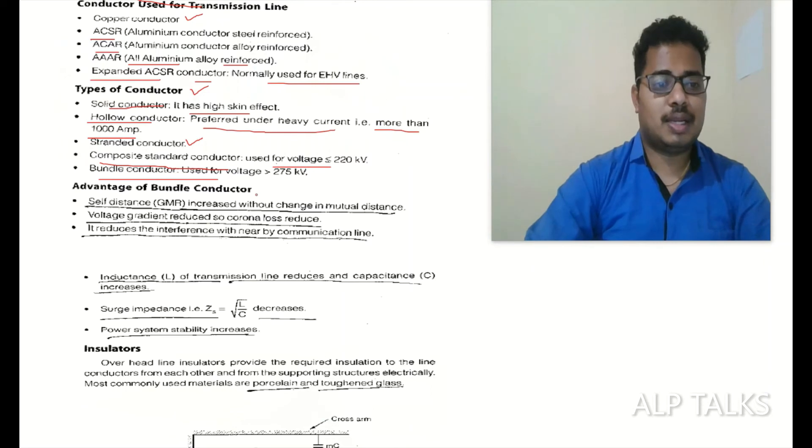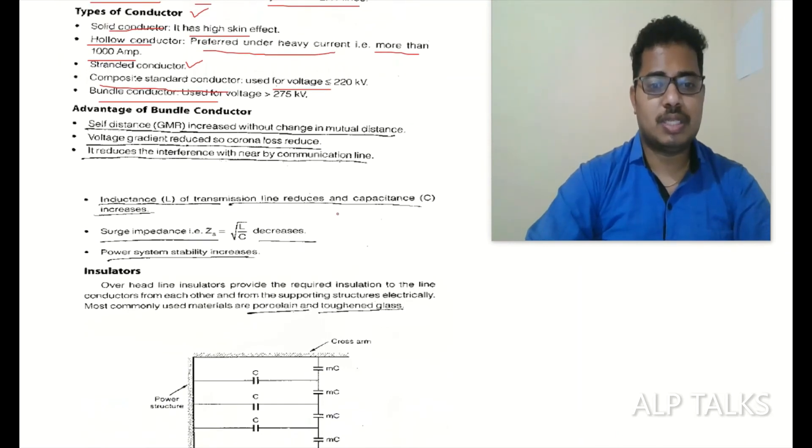Advantages of bundle conductor: self GMR increased without change in mutual distance, voltage gradient reduced so corona loss reduced, it reduces the interference with nearby communication lines, inductance of transmission line reduces and the capacitance increases, surge impedance Zs equal to square root of L by C decreases, power system stability increases.